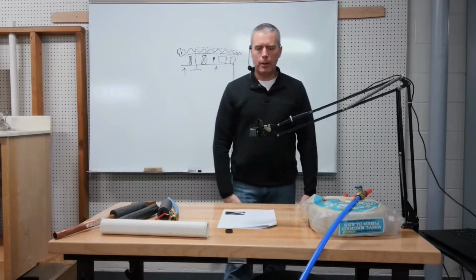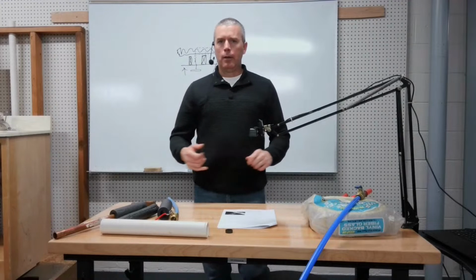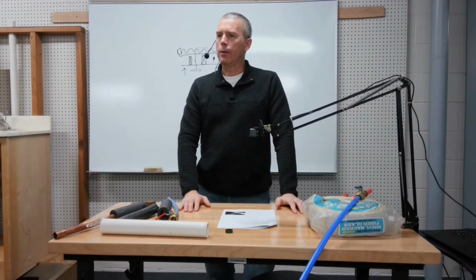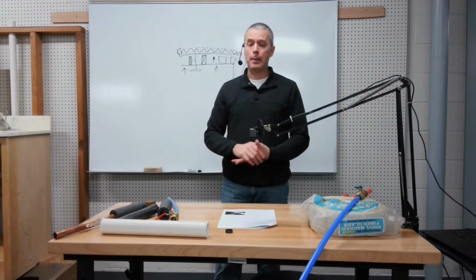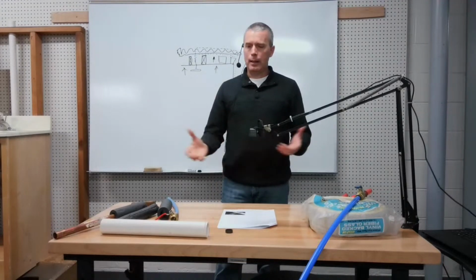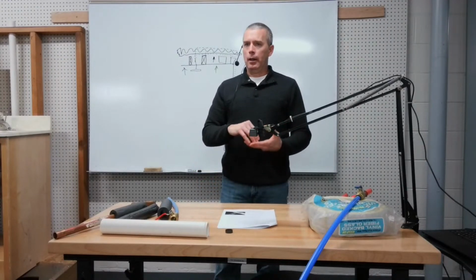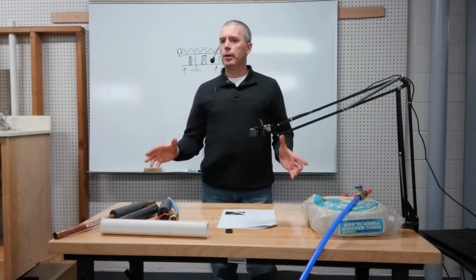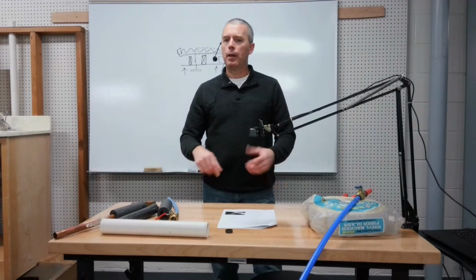So underground, I think we talked about this a little earlier today, before the meeting. Water freezing underground. So you're supposed to have your water lines buried deep enough so that they don't freeze. I think it's like 60 inches. It's been a long time since I've run a water main, but I think it's 60 inches, so 5 feet deep, to be below the frost line. In wintertime, when there's no snow and you get the super cold weather, that cold just slowly creeps down into the ground, and it gets down to where the water lines are at, and they'll rupture, they'll freeze.